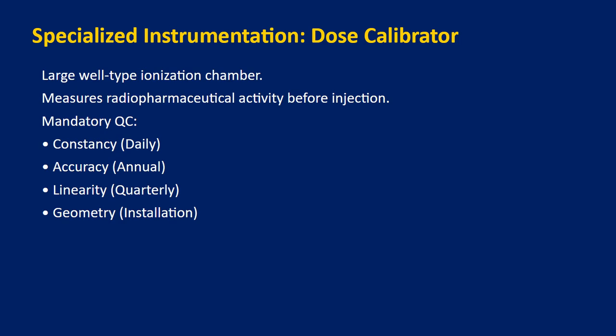You must check consistency every single morning to ensure the meter has not drifted. You must verify accuracy once a year. You must prove linearity every quarter to show the meter works at both high and low activities. And finally, you must check geometry to ensure that the same amount of activity reads correctly whether it is in a tiny vial or a large syringe.